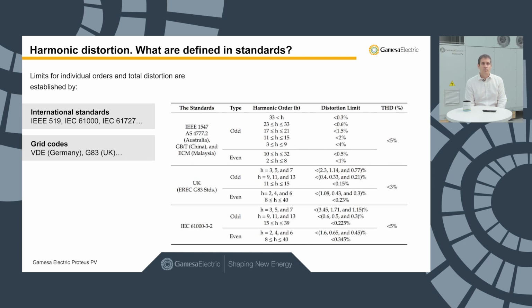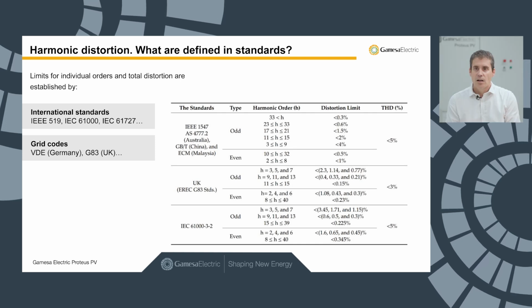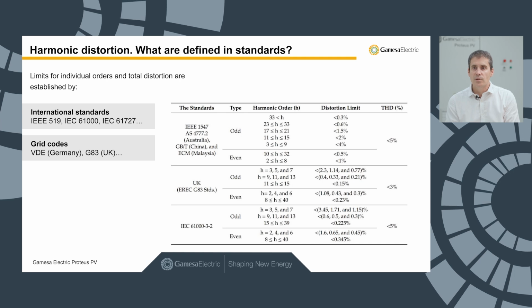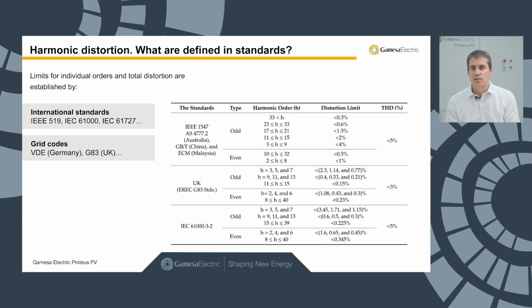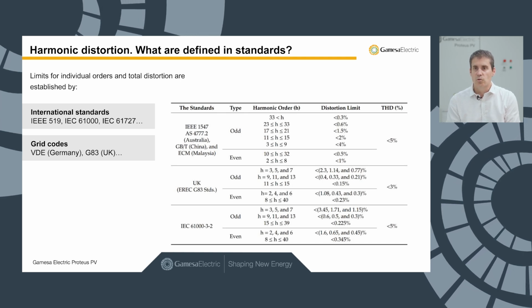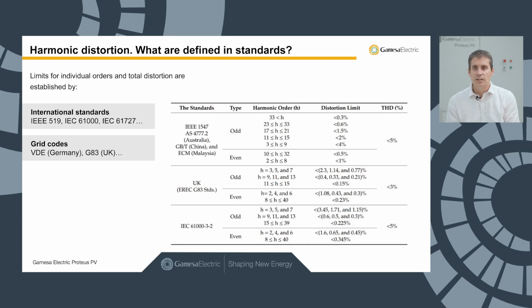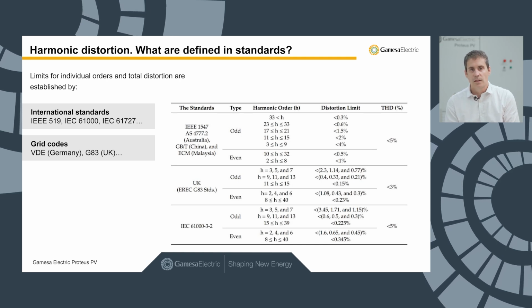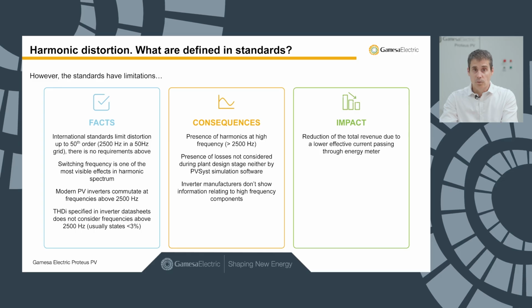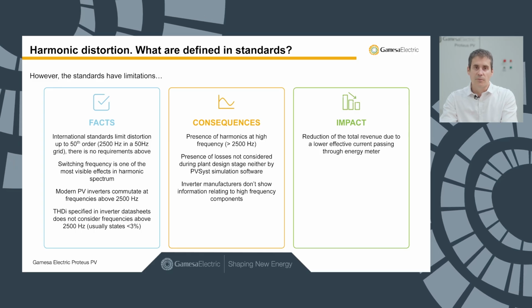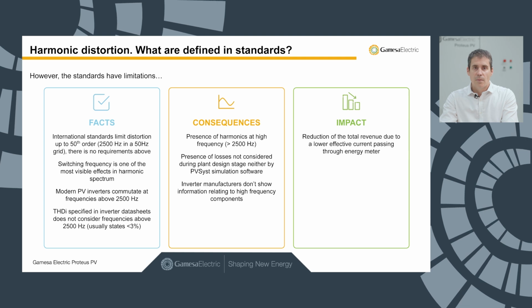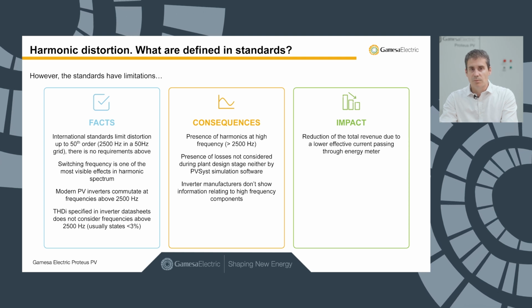Sometimes the technology goes a little beyond the standards. For this particular case, the switching frequency of the inverters is higher than the measured limits established by the standard. So solar inverters can fulfill the standards while having a poor THD. Why do we say that? Because the standards limit the distortion only up to the 50th harmonic, so 2500 Hz in a 50 Hz grid. There's no requirement above this value.